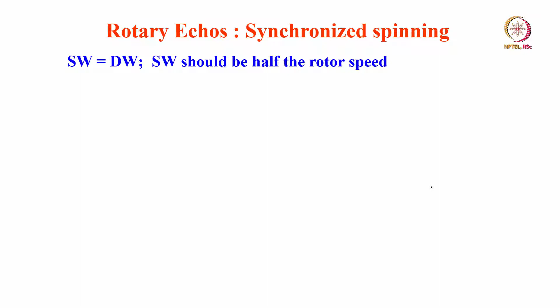The second method is called the rotary echo. This is what I said, rotor synchronization. While spinning is going on, I can synchronize with the spinning and acquire the signal, every time it goes for one rotation. We discussed the rotary echo. The rotary echo comes exactly at the spinning period. When the rotor starts here, let us say this is the marker, when it rotates and comes exactly to the same place where it started, you are going to see an echo pattern here. This is called a rotary echo. And it keeps going like this as you keep on acquiring the FID, and it decays with time.